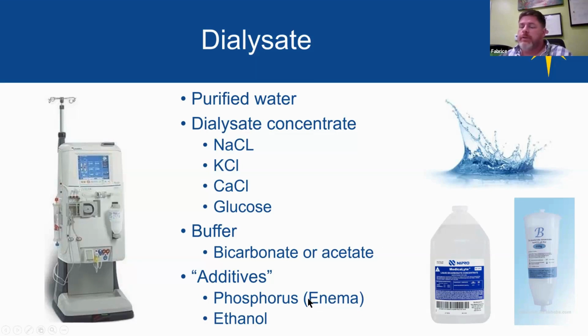And a funny fact is that we actually use enemas for that, the Fleet enema, because they have a high concentration of phosphorus. And so we add them to the acid concentrate, depending on the amount of phosphorus we want. We have some rules, and that's how we actually add phosphorus. And the other thing is that when we have an ethylene glycol intoxication, we can add ethanol in the acid concentrate, and that would allow us to also dialyze the patient and treat the intoxication.